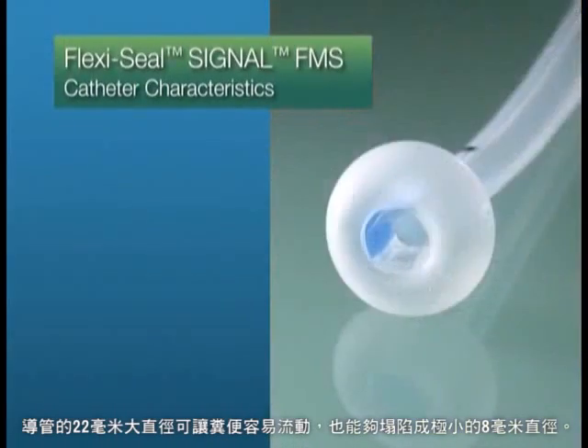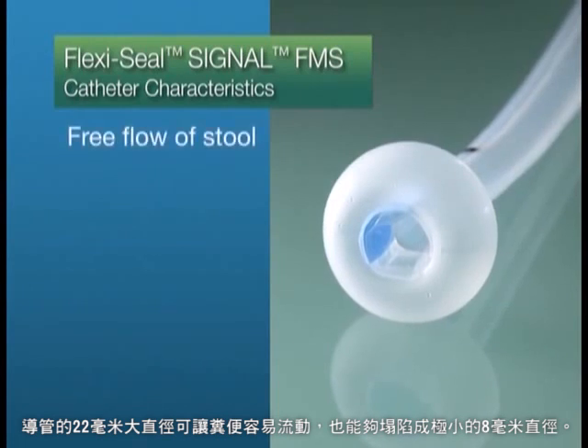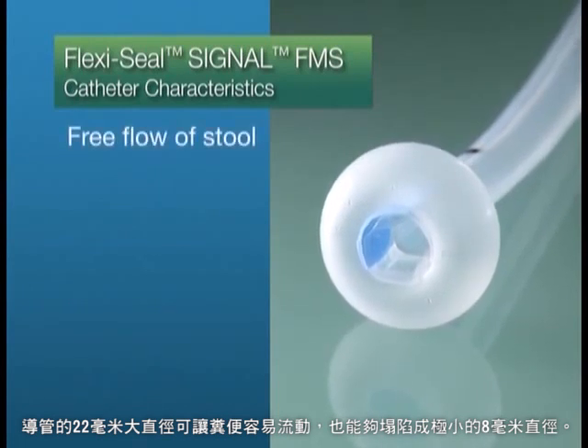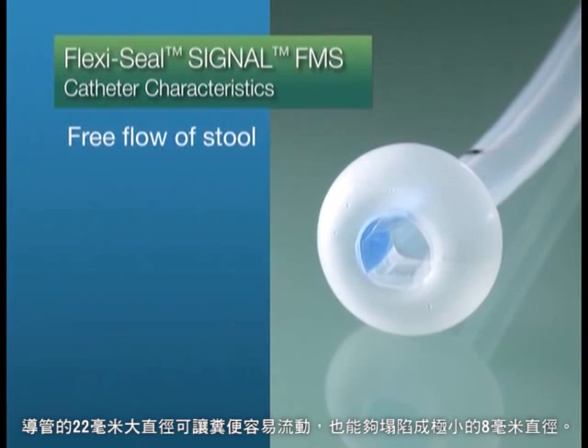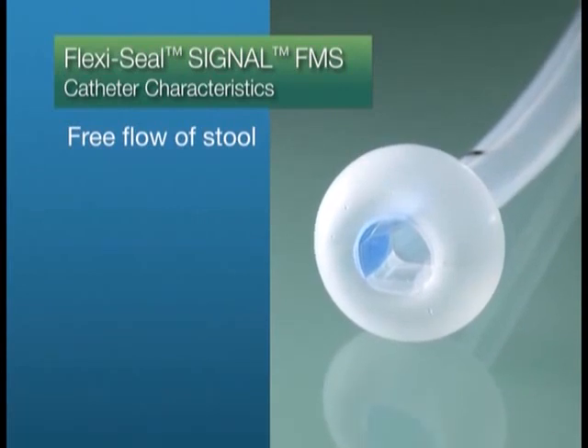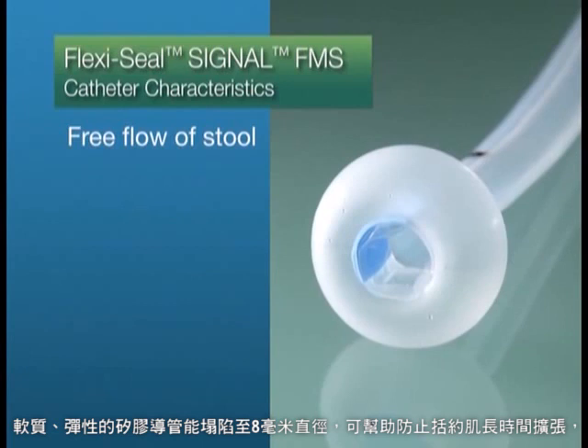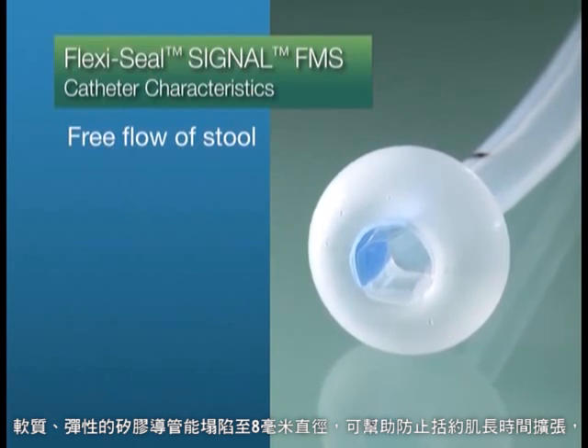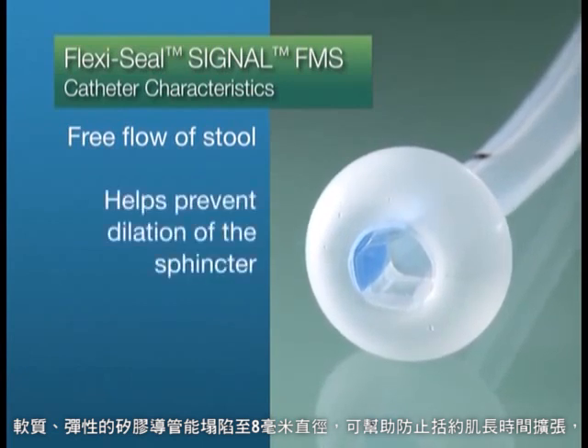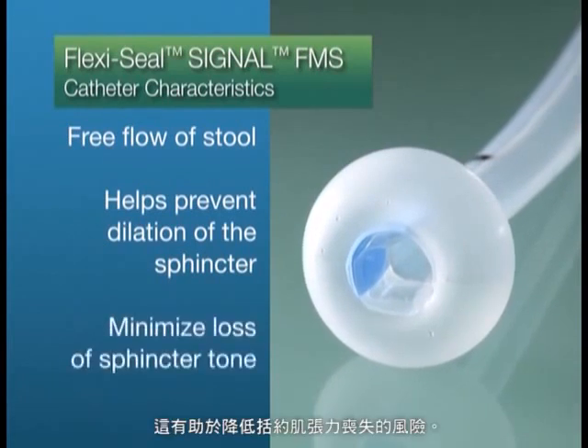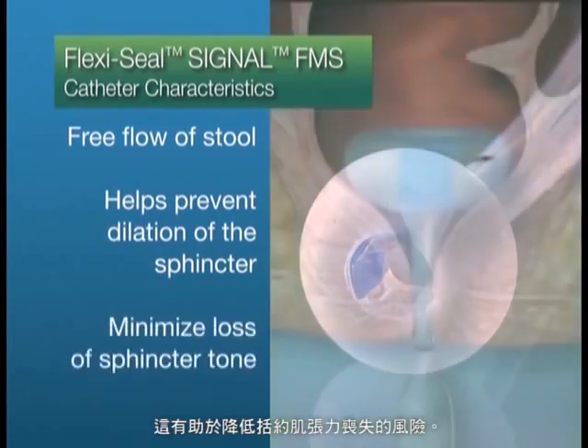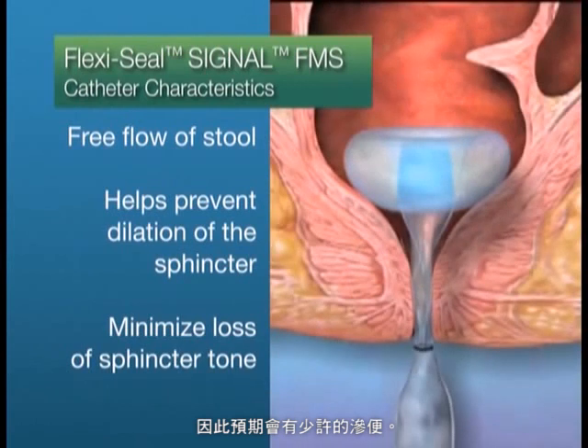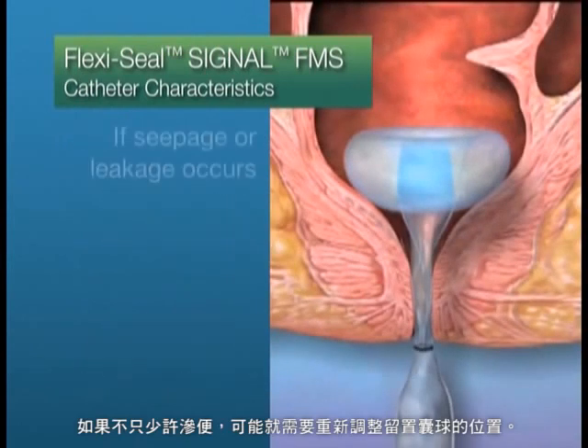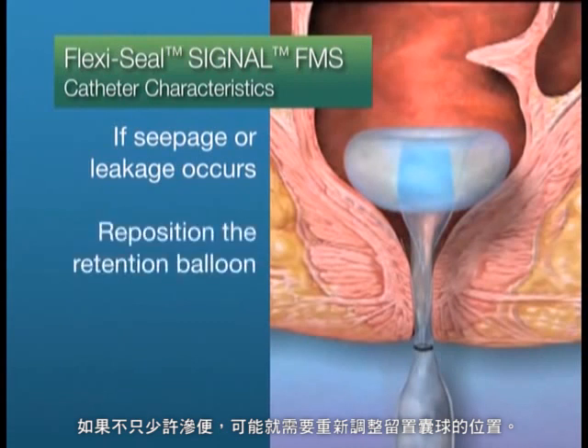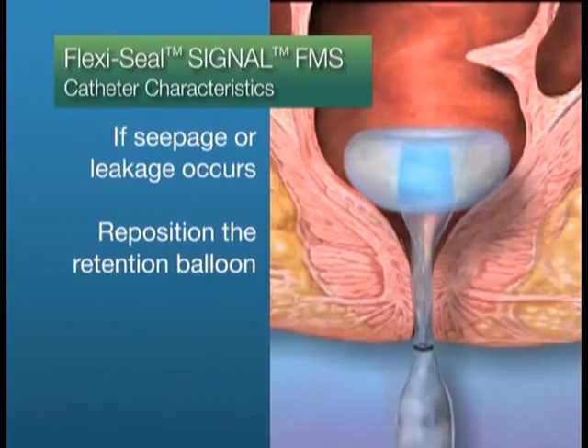The catheter's large 22 mm diameter is designed for free flow of stool and is capable of collapsing to a very small 8 mm diameter. This ability of the soft, flexible silicone catheter to collapse to an 8 mm diameter helps to prevent prolonged dilation of the sphincter, helping minimize the risk of loss of sphincter tone. A small amount of seepage is therefore expected. If more than a small amount of leakage occurs, this is likely a sign that the retention balloon should be repositioned.